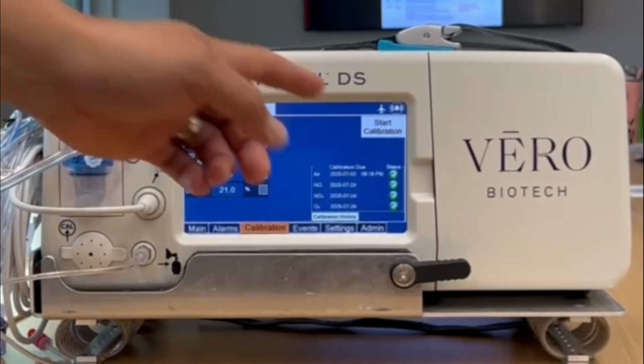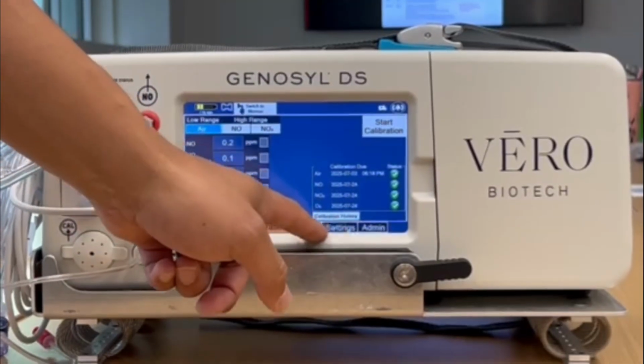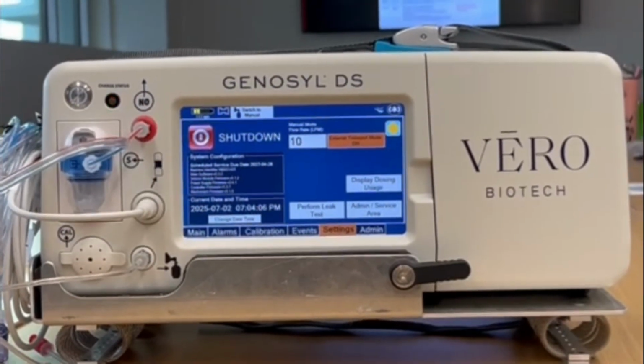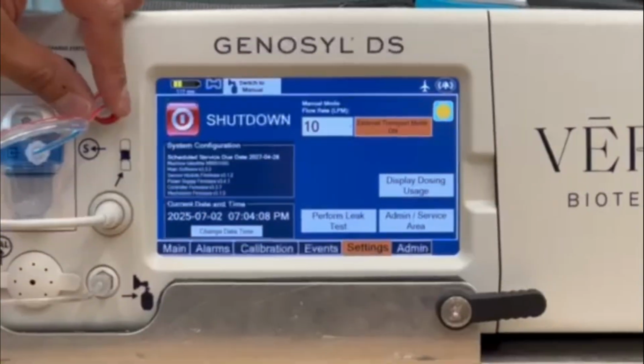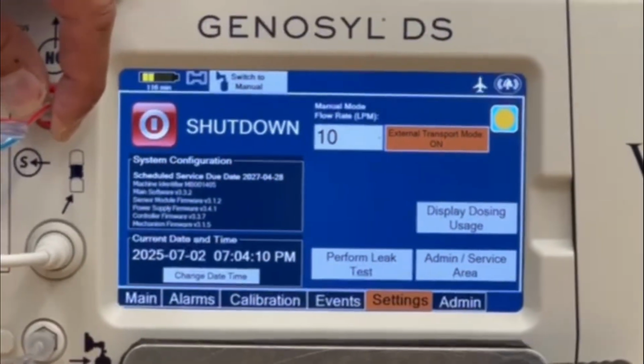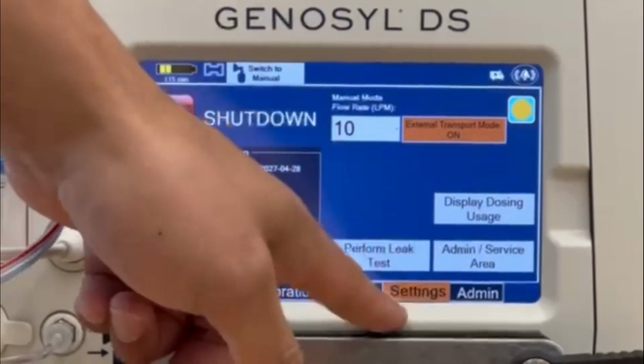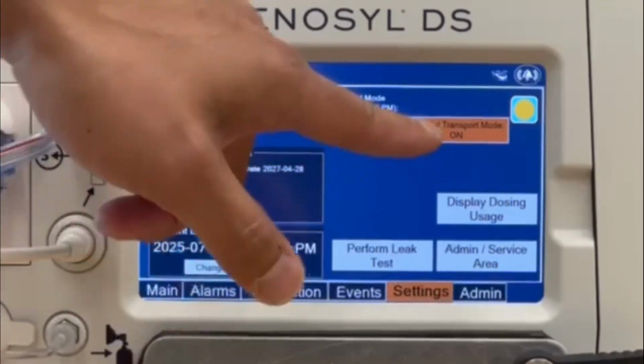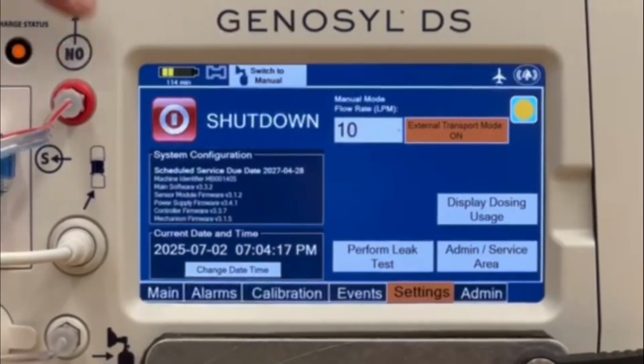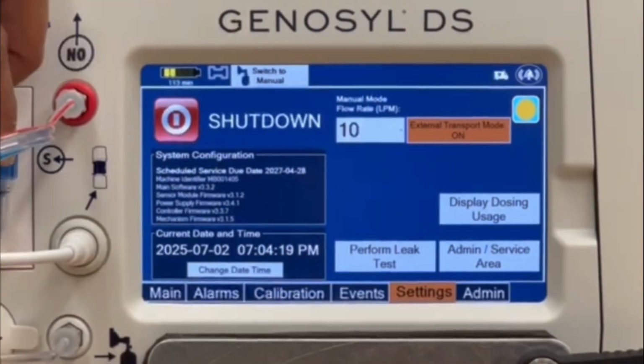Another added benefit is under the settings tab, if there is a leak detected, it will alarm, like if you have a low NO alarm. If you swing over to the settings tab, it'll say leak detected here. So that's your cue to double check your lines and make sure there's no leaks.